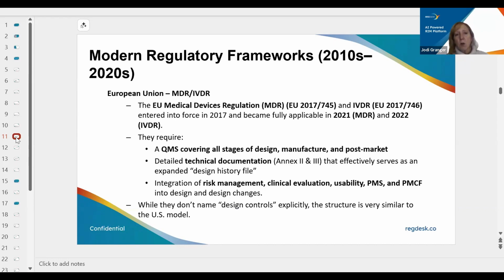The updates required your quality management system to cover all stages of your design, manufacture, and post-market processes. They detailed technical documentation within Annex 2 and 3 that effectively serves as an expanded design history file. So it's really important that you understand those annexes and how they pertain. They also have integrated risk management, clinical evaluation, usability, PMS, and PMCF requirements as well.